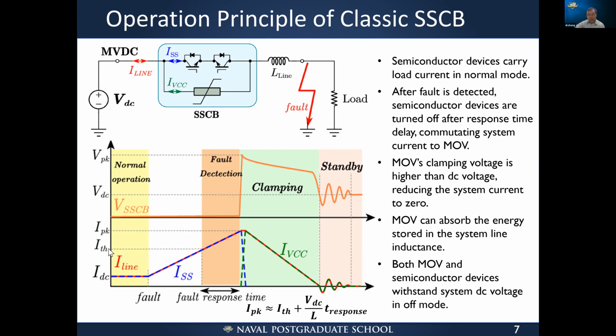So once the current exceeds certain threshold levels, ITH, the fault has been detected. But it will take a while, depending on the response times in the systems. The current will keep increasing until, after the delays of the response times, the devices will be turned off. Once the device is turned off, the IGBT current will reduce to 0, and the system current will be commutated to the MOV branches.